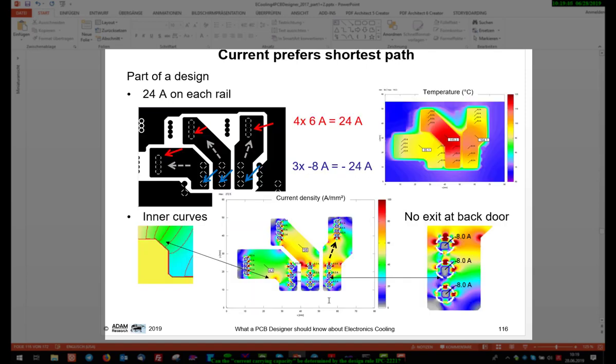This is an example of a detailed calculation. We have a current of 24 amps in each of these three traces. Each trace has an individual temperature. Each trace has an individual current density pattern. And it's impossible to get the temperature of the three traces by just reading the IPC graphs.